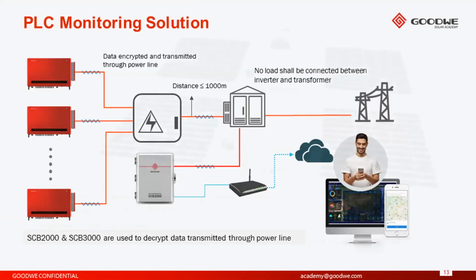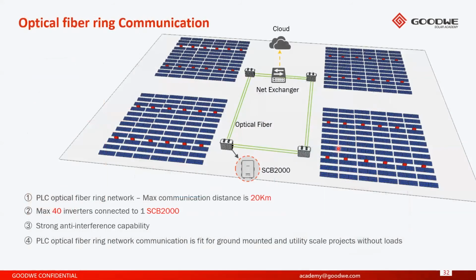You're able to extend the communication using an optical fiber ring. So if you have a number of PV plants in different sites, which are quite close to each other, or if you have more than 40 or more than 60 inverters on site, you can use multiple GoodWe monitoring solutions such as the EasyLogger Pro or the SCB and connect them together with an optical fiber cable, so that you have a large PV plant communicating with each other.